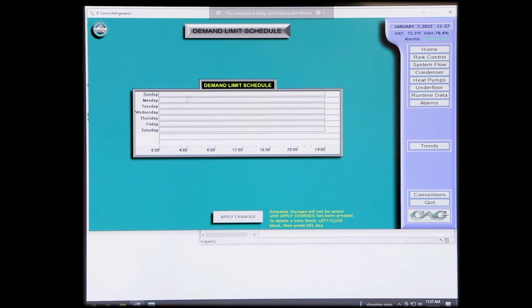As you can see, there's already one set in here, and you can go ahead and change that if you like. You can set this so that you can mimic your night schedule if you wanted. You can have 3 machines during your day default period, but yet only have 2 machines at night. You can mimic and change that demand limit schedule and enable the schedule and only have that happen at night. All right? If you so chose, if you wanted to.